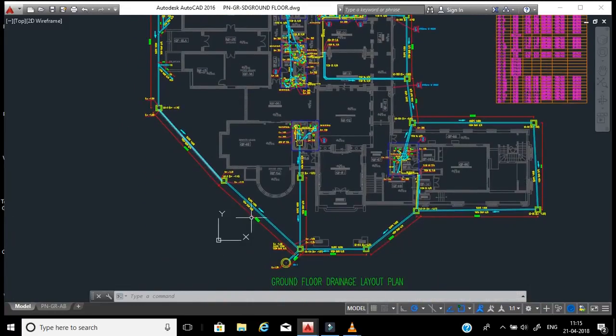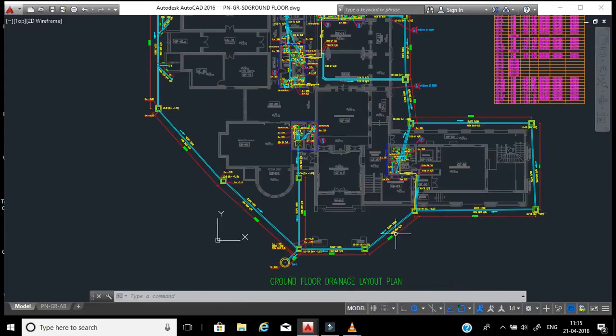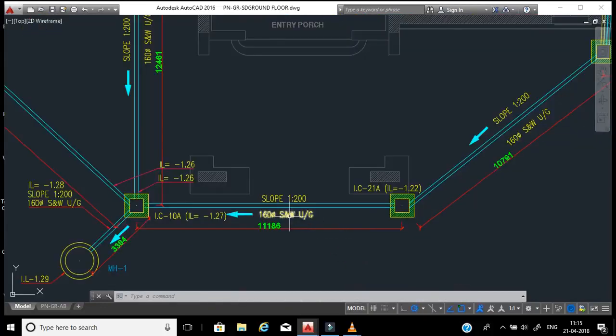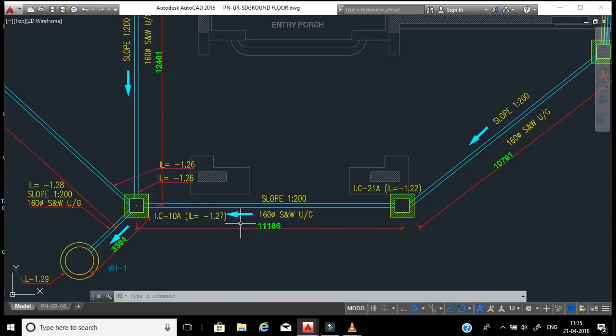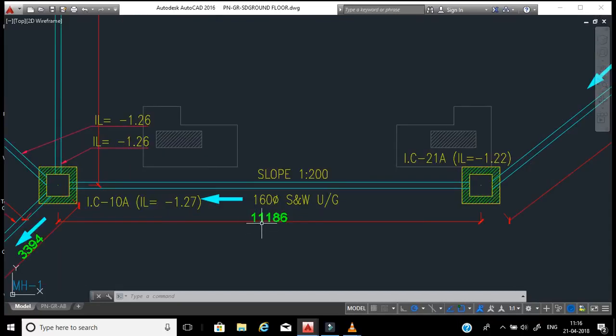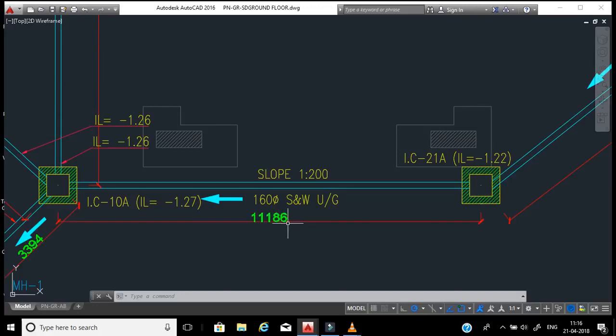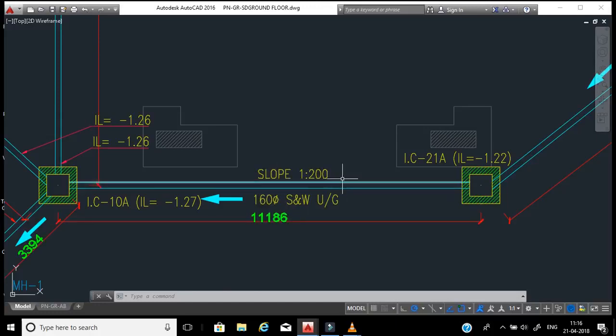For example, this manhole line is starting from here going until here, and the slope coming to here is 1 to 200. What is 1 to 200? It means when a pipe passes 200 meters, we need to provide 1 meter of slope downward. This is a plan view. Our pipe length here is 11,186mm - that is 11.186 meters. We need to convert this slope for this 11-meter length.